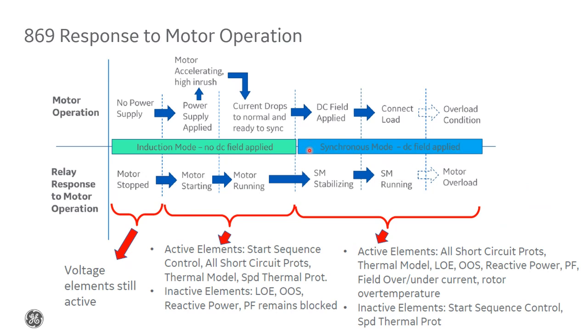So at this point, when we apply the DC field, all the usual protection elements are enabled, and those related to starting, like the start sequence control and the speed dependent thermal protection, become inactive. And then from here on onward, we're in normal synchronous motor running mode, and the relay continues to monitor for an overload or an abnormal condition.